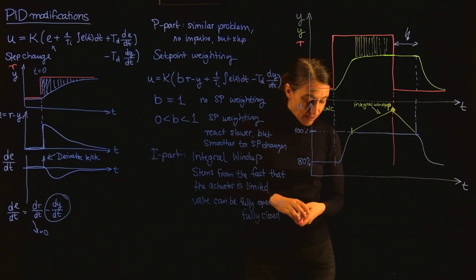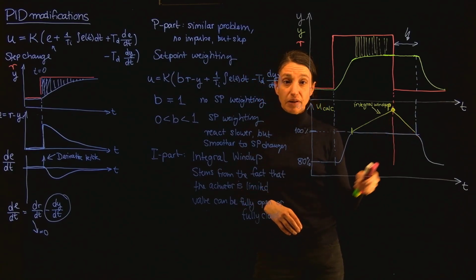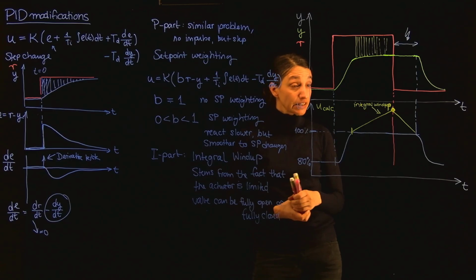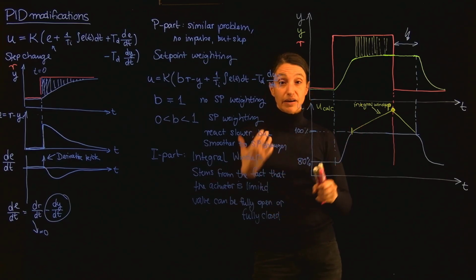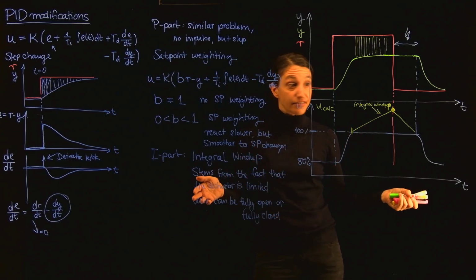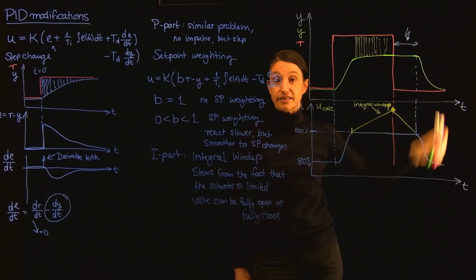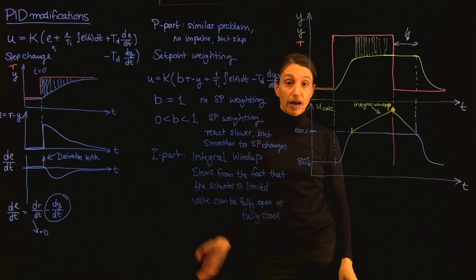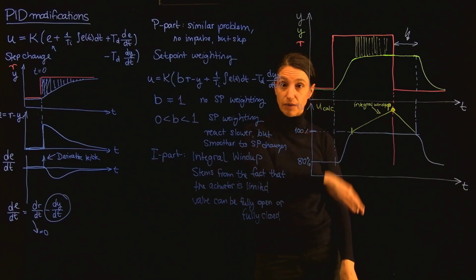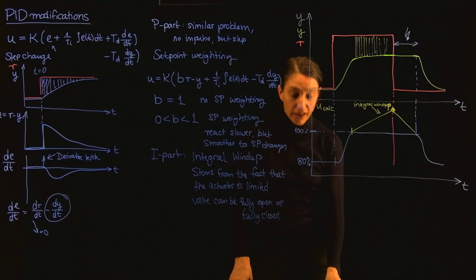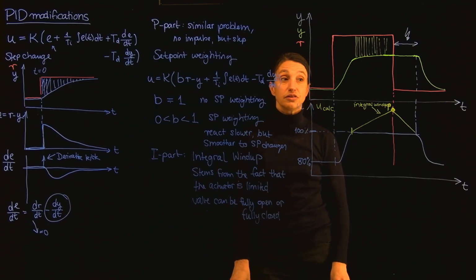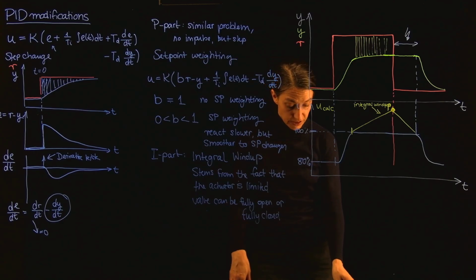So you think, oh, is this really so terrible? And the answer is yes, it's terrible, because think about someone leaving it on for a couple of days. Think how high this has gone up, it's shot up, and you will never get it down. If it's been high up, you will have to wait another 2 days for it to come down. You're thinking, oh, my controller is not working. So it is not optional to not deal with integral wind up. Fortunately, it's actually very simple. You just have to know about it, and this is the difficulty.